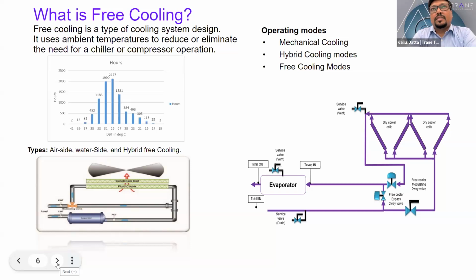Now, this typical bar chart shows that at 35-degree dry bulb temperatures, out of 8,600 hours in a year, we can almost encash 6,500 hours for free cooling. And that's the perfect example of an area or climatic condition for free cooling application.